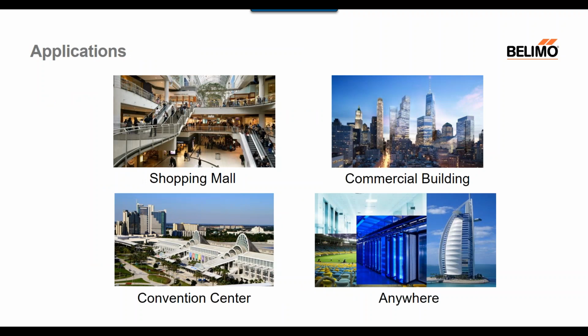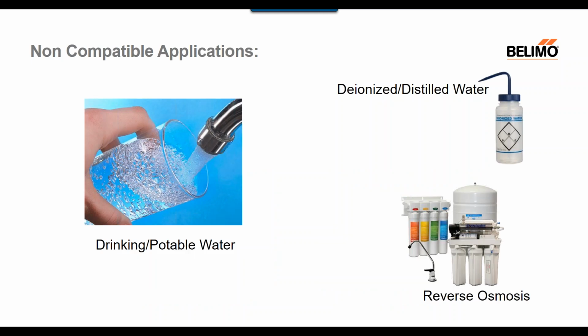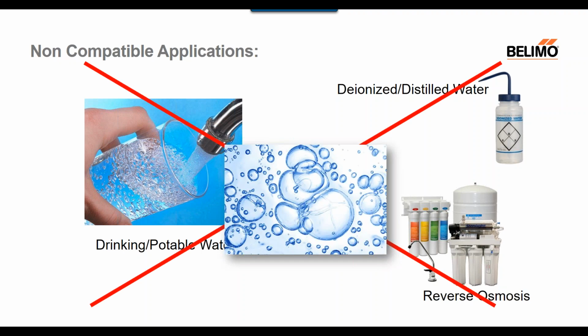Applications and building types include shopping malls, commercial buildings, convention centers, data centers, hotels, stadiums, basically any application and location where you really need to know the true flow of any system. Applications where not to use the flow sensors include distilled or deionized water, drinking potable water, and also reverse osmosis. Reasons include degrading of the flow sensor housing, the mirrors, possibly the transmitters and receivers, and also air bubbles causing inaccuracies.